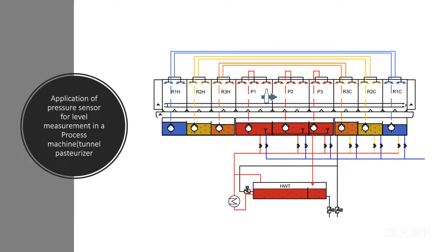Okay, if you look at the next slide, this is just a P&ID drawing for a tunnel pasteurizer. In a tunnel pasteurizer like this, from the R1H zone down to the R1C zone, you have water in the tanks. This level needs to be maintained during production in industries. The same applies to R2H to R3, R2C, and vice versa. They are recuperating each other. So in industries, we use the level sensor to ensure a stable, sustained and equal level in both tanks. During production, both pumps are running, but we want to achieve level balance in both tanks. So this is also an application of it in industry.